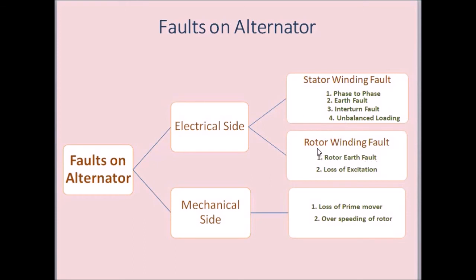On the rotor winding, there may be a possibility of a rotor-to-earth fault, meaning insulation failure between the rotor winding and the rotor core, leading to a rotor earth fault. There is also a chance of loss of excitation to the rotor, meaning the DC current fed to the rotor can be lost by any means.